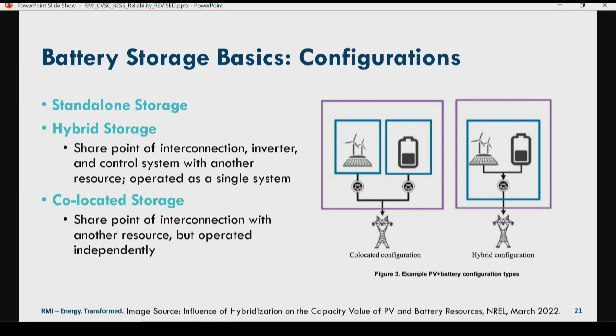There are several different types of configurations for battery storage as well. The most straightforward is standalone storage, in which storage is developed independently of any other resource. There are also hybrid storage configurations, in which storage shares a point of interconnection, an inverter, and a control system with another resource, and this is operated as a single system. So from the perspective of the grid operator, they see a single resource which they can control. That's presented on the right in this figure. Storage can also be co-located with other resources, in which they share a point of interconnection, but are operated independently by the grid operator and are seen independently.